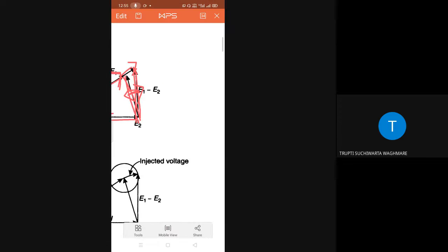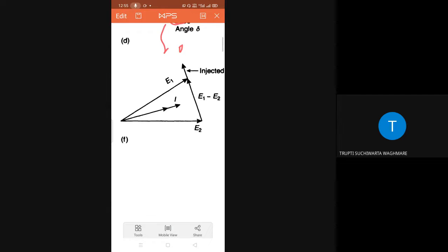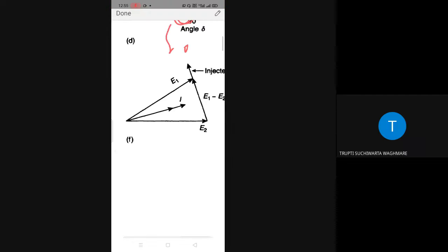But rather than changing the voltage at the end of the line, if we change the voltage drop across the transmission line without changing the end voltages, I will keep the end voltages as they are, but I am injecting some voltage in series with the transmission line such that it is in phase with the voltage drop across the transmission line. So I injected this much magnitude of voltage in series with the line, in phase with the voltage drop across the transmission line. So because of this, what happened?